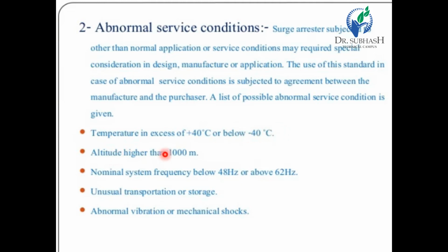Altitude greater than 1000 meter is also abnormal. Nominal system frequency below 48 Hz or above 62 Hz is also considered as abnormal condition. Unusual transportation or storage, abnormal vibration or mechanical shocks. So these are the typical abnormal service conditions.